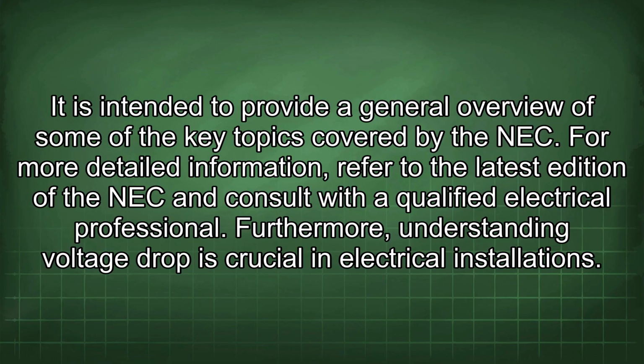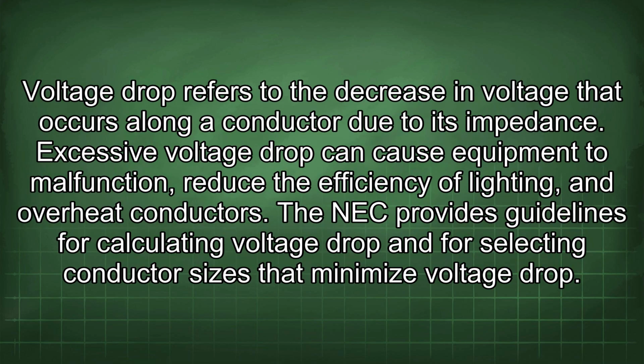Furthermore, understanding voltage drop is crucial in electrical installations. Voltage drop refers to the decrease in voltage that occurs along a conductor due to its impedance. Excessive voltage drop can cause equipment to malfunction, reduce the efficiency of lighting, and overheat conductors. The NEC provides guidelines for calculating voltage drop and for selecting conductor sizes that minimize voltage drop.